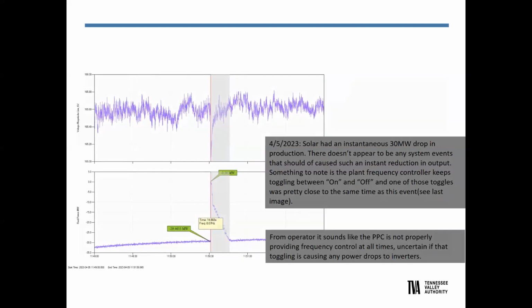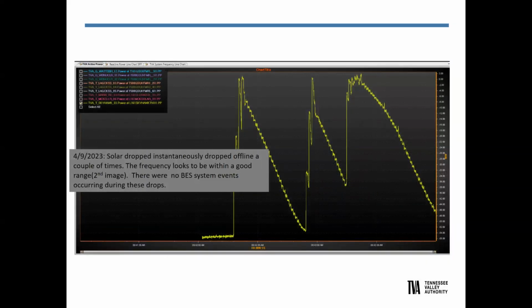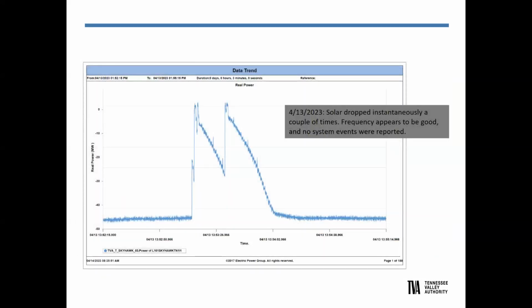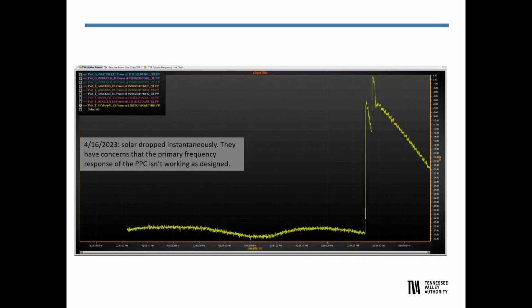If you go to the next slide, these next four events here are all caused by the operator trying to fix the previous ramp rate, 10 megawatts per minute ramp rate. If you look at this one, this is a pretty large oscillation on reactive and megawatt dropout. If you go to the next slide, there's another set here about a week later as they work through the tuning problems. And if you go to the last one here, they dropped out instantaneously. Again, the frequency response of the PPC is not working as they designed it.